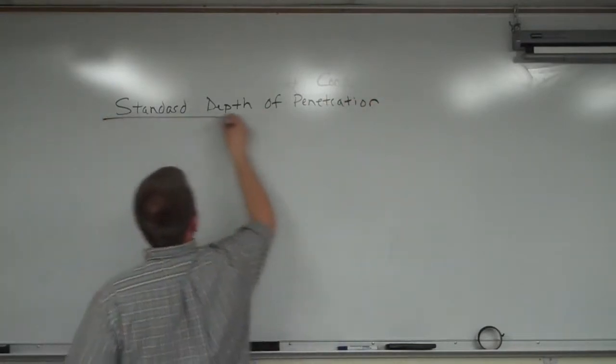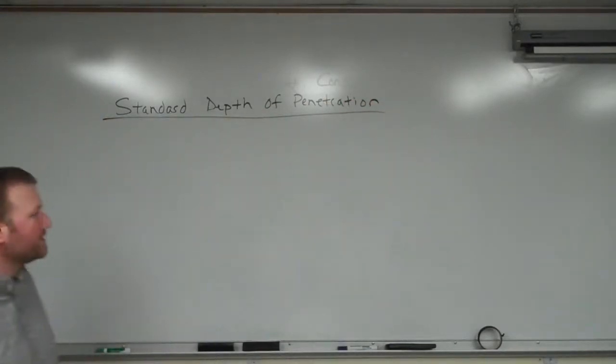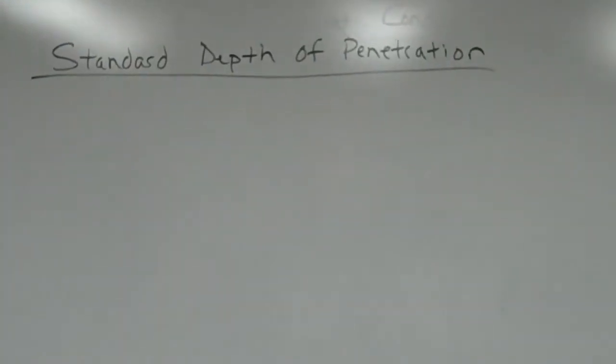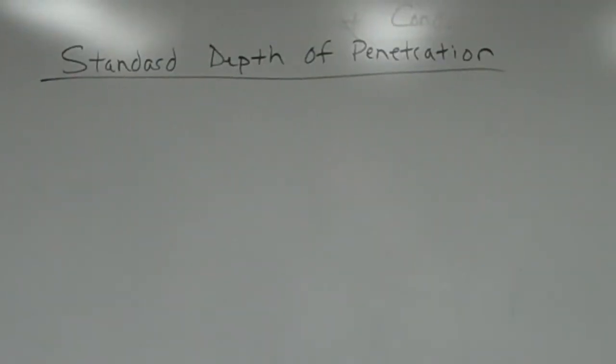The last set of calculations we're going to deal with in eddy current is standard depth of penetration, at least for right now. Just basic numbers. This isn't necessarily going to be the most perfect thing, and it isn't always going to be perfectly correct, but it's going to give us a good view of what's going on in a part.